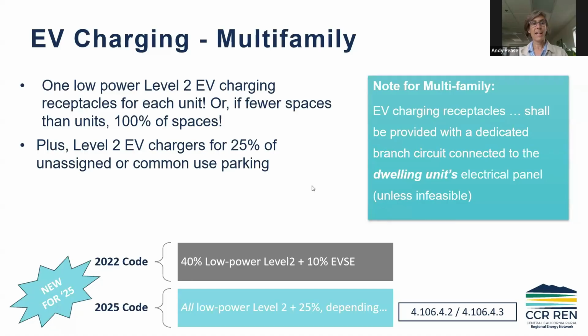In multifamily, now it is 1 low power level 2 EV charging receptacle for every unit. This is a big change. If it's fewer spaces than units, then it's all of the spaces. And if you've got more unused parking spaces than units, then 25% of those have to have actual EV chargers. And note that if possible, the EV charging receptacle for an assigned space to a unit should be wired to that dwelling unit so that occupant's electric bill includes the electricity for charging their vehicle.